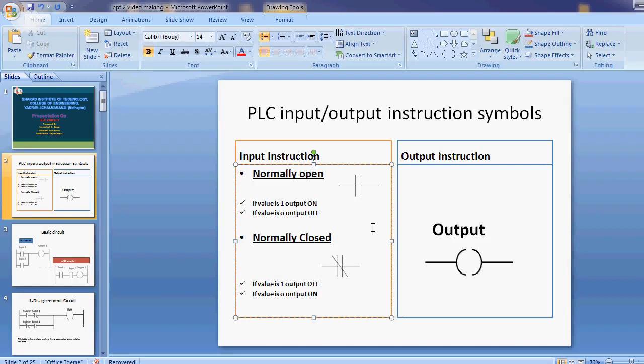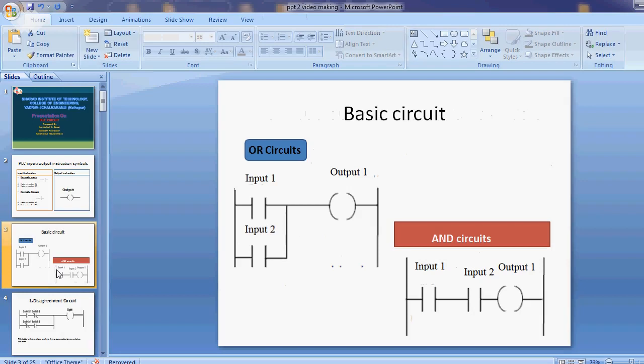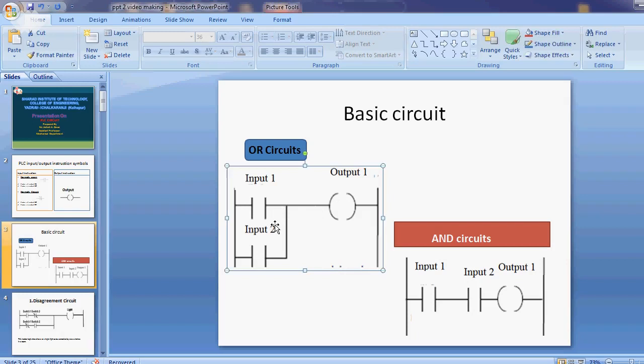Now we discuss the next case — the basic circuits. We draw basic OR and AND circuits. These two vertical lines are called power rails. When the two normally open contacts are in a parallel manner, these are called OR circuits. If input 1 is ON, output 1 is ON. If input 2 is ON, output 1 is ON — meaning any one of the switches or inputs being ON will turn the output ON.